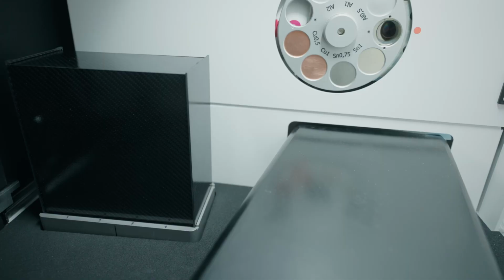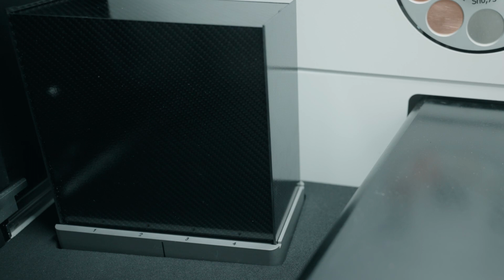If we have a look inside the machine, we'll see that the object sits nicely in a pre-cut foam pocket in the corner of the cabinet. Underneath the object itself is the fixturing device for the calibration object. Upon closer inspection, you'll notice that both the object itself and its fixturing device are numbered 1 through 4. These will become useful later. The fixturing device also has 3 notches underneath, just like the fixturing plates that came with the system. This once again allows us stability when placing the calibration object on the rotation table.